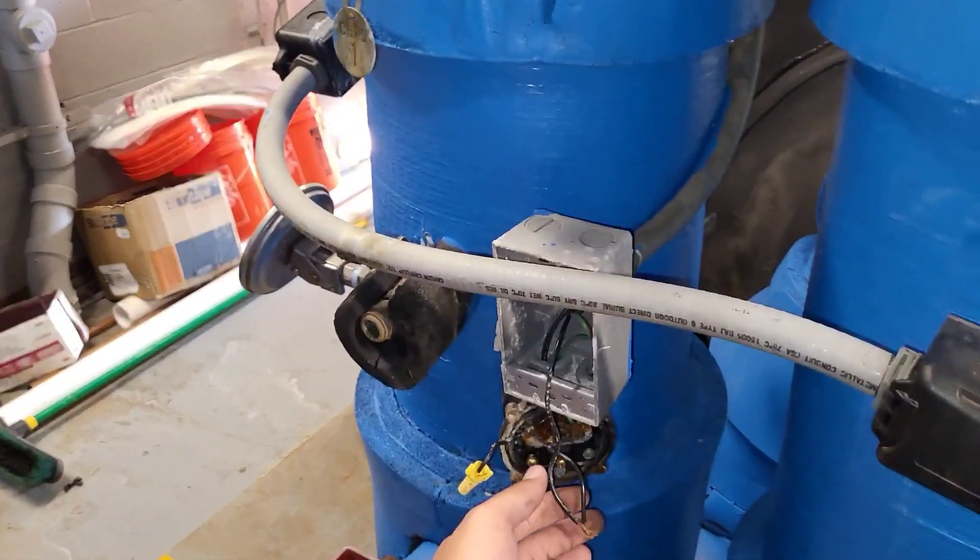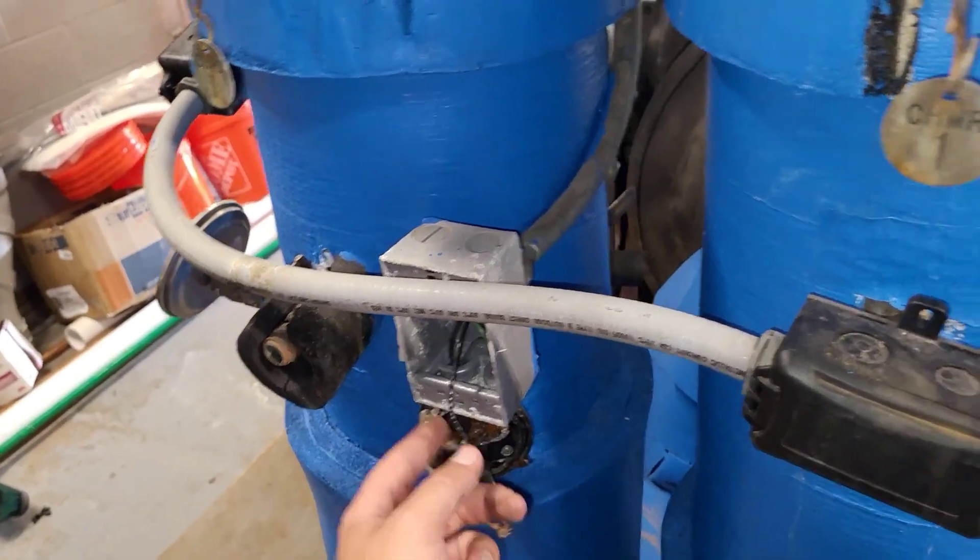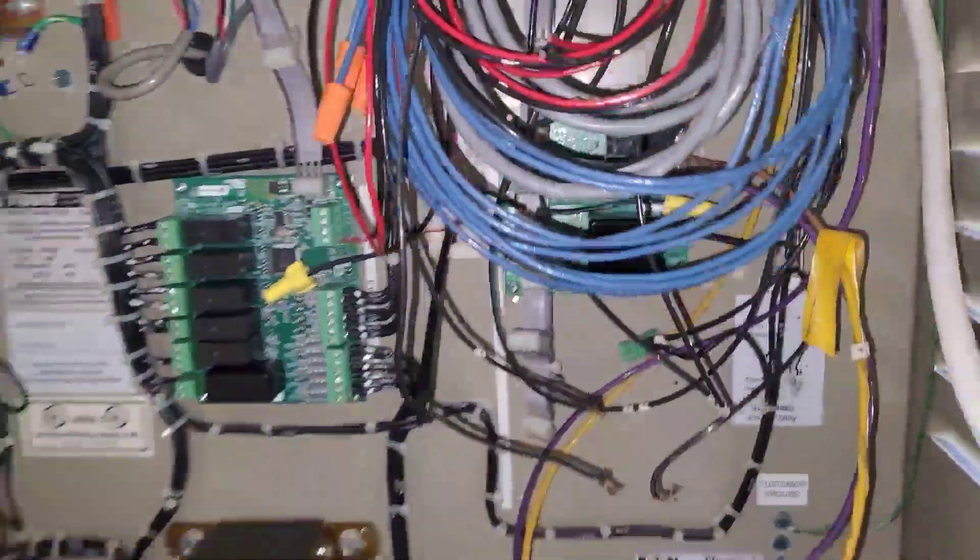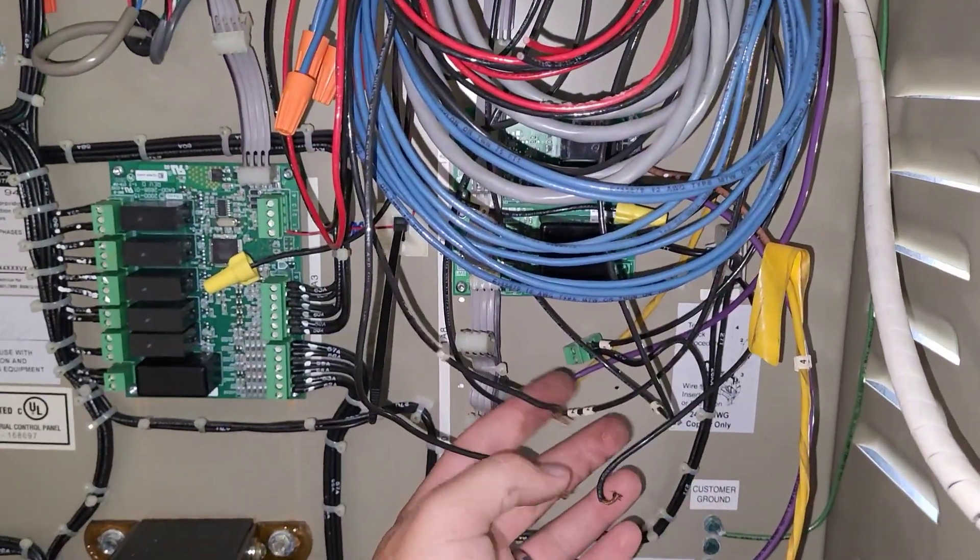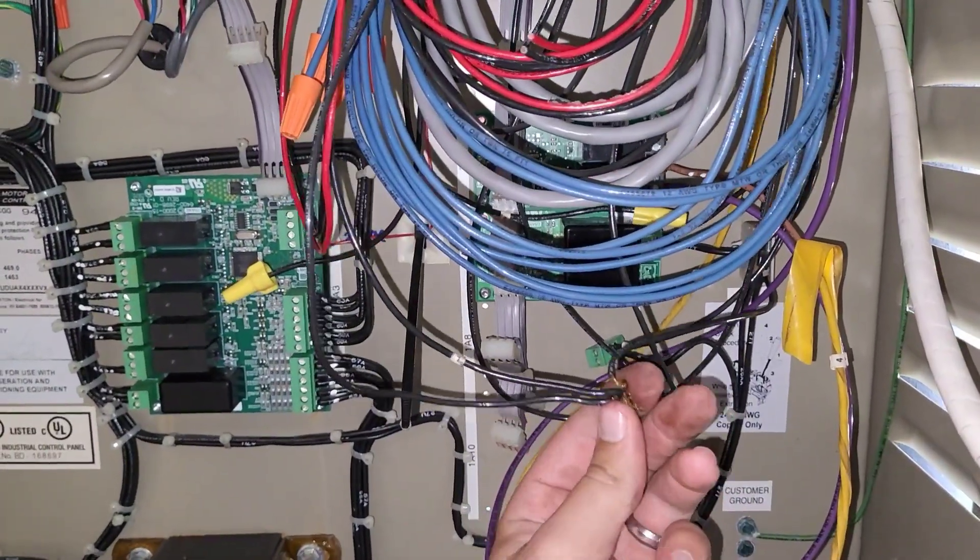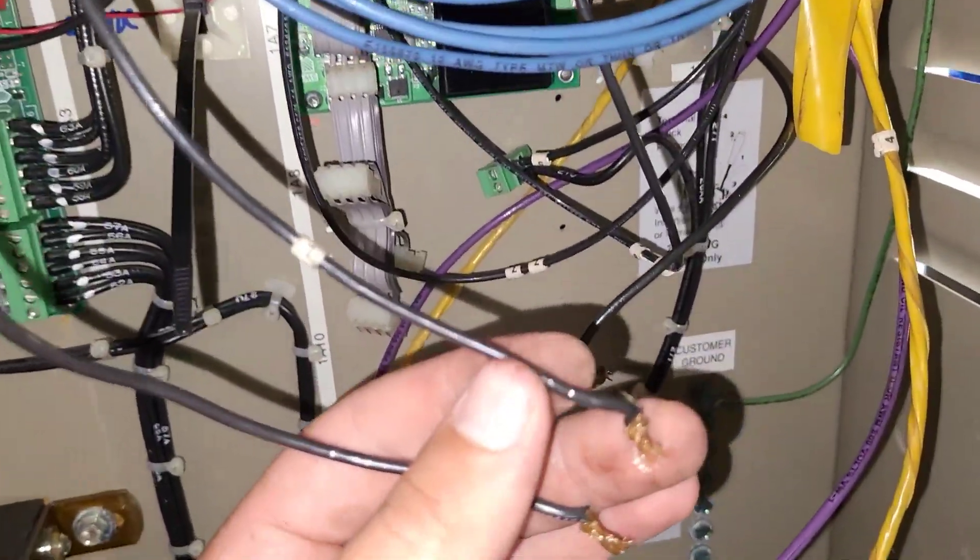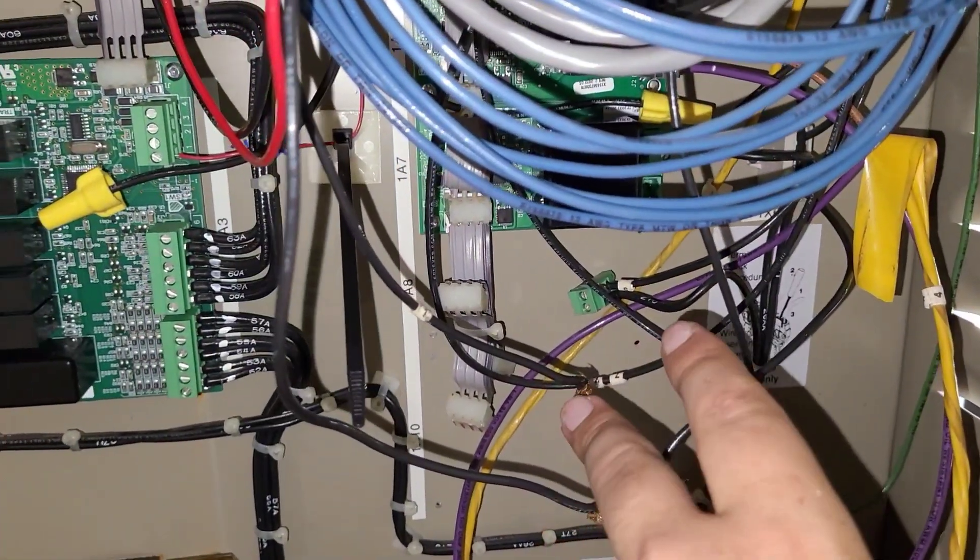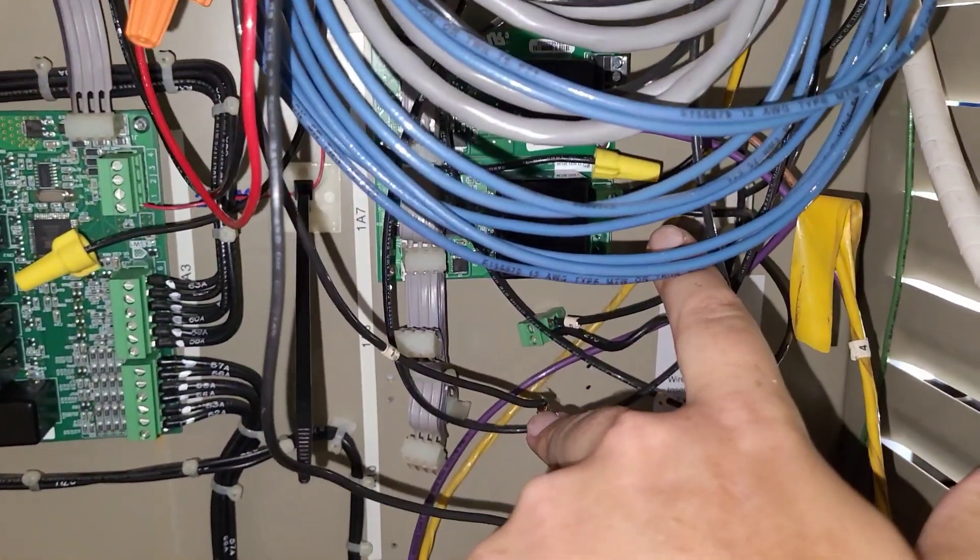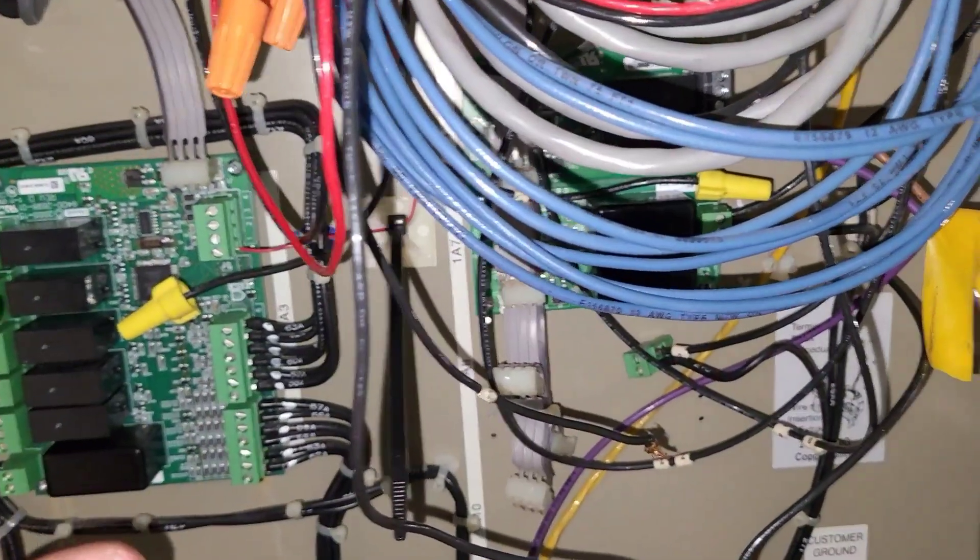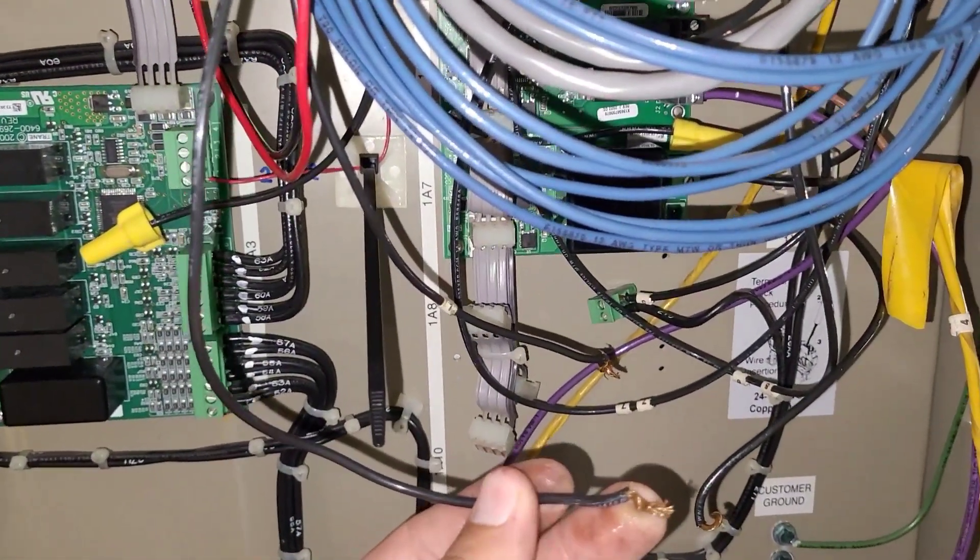I start checking it here and I'm still seeing a short on one of these legs. So testing it back, I go back through the switch. I was testing between the switch and the panel getting ready to condemn one of those wires. I shorted the ground. That brought me back to this point here. These three wires tie together, and these are the commons of both the condenser and the chill water flow switch. Out of being thorough, I pulled all the connections apart from each other and was testing across just the chill water wires and then testing both wires to ground. I lost my short to ground. So then I tested it on the condenser water side, and sure enough the short was back.